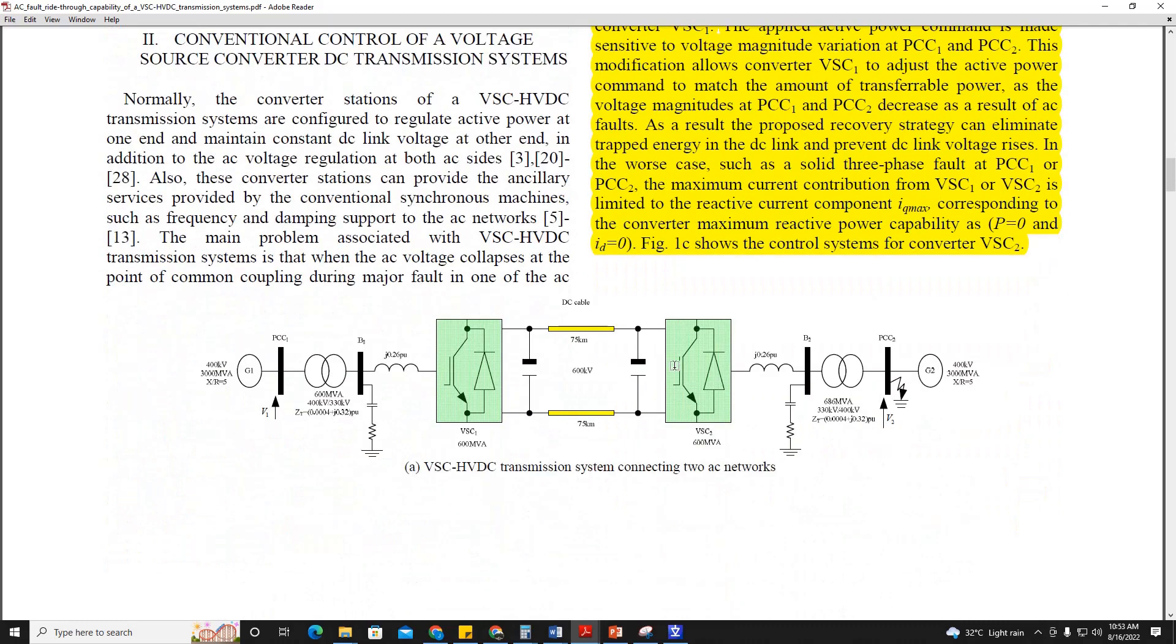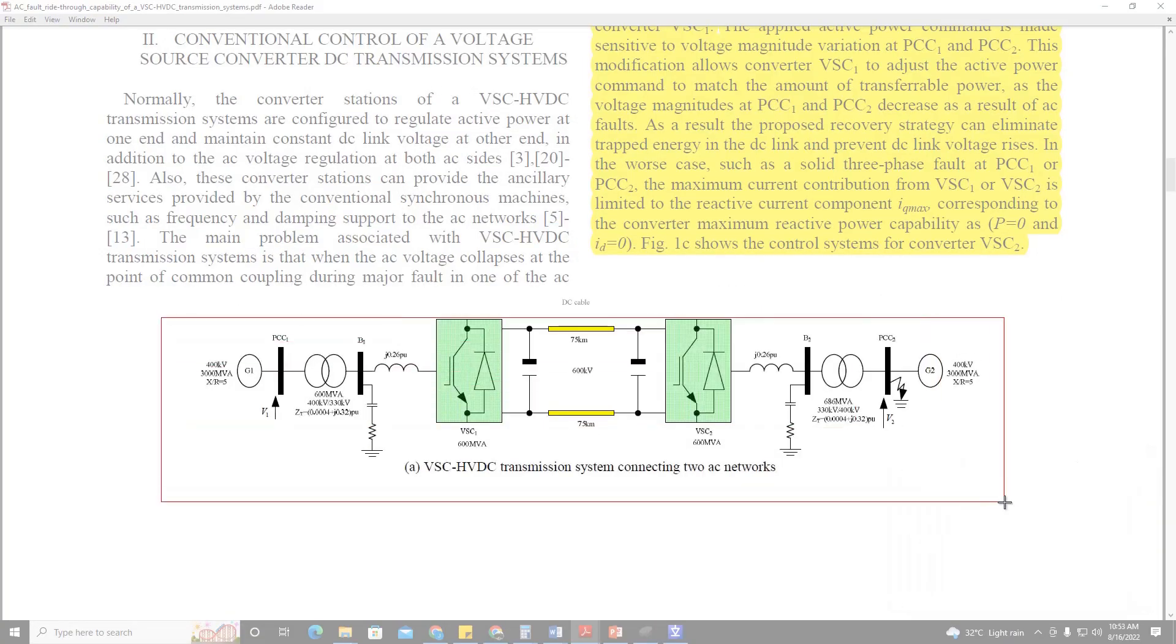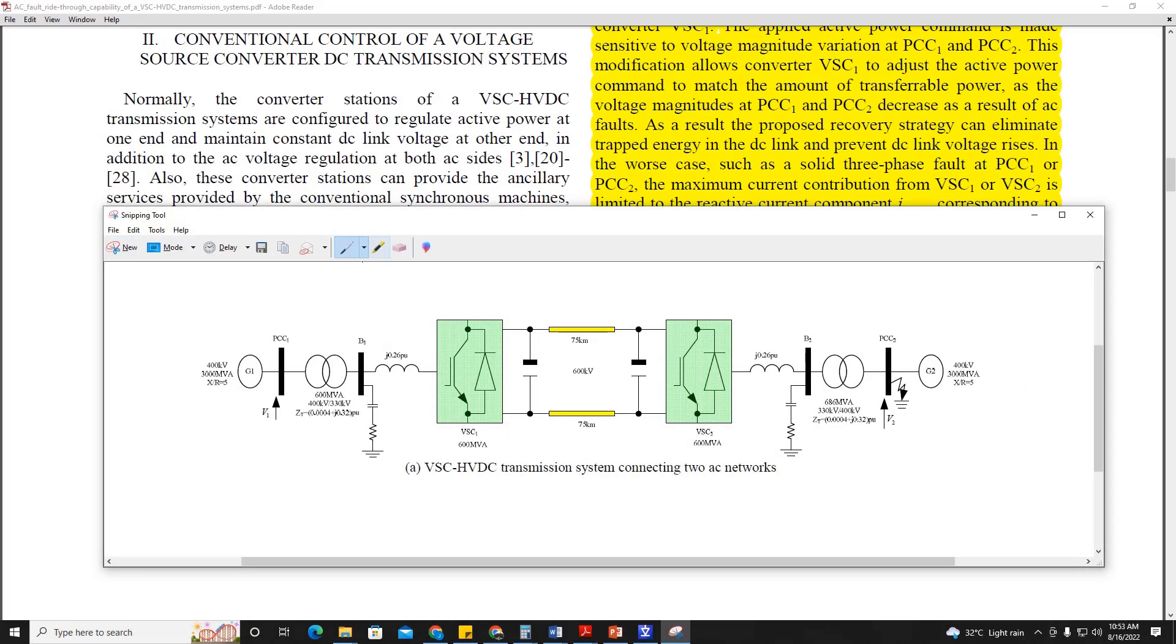So this is a model. This is a single line diagram of the model used in this research paper. Right now, as we can see, the fault is happening here at point of common coupling 2, V2, at grid 2. This is a voltage source converter, not MMC, and SPWM sinusoidal pulse width modulation is used at a switching frequency of 2.1 kHz.